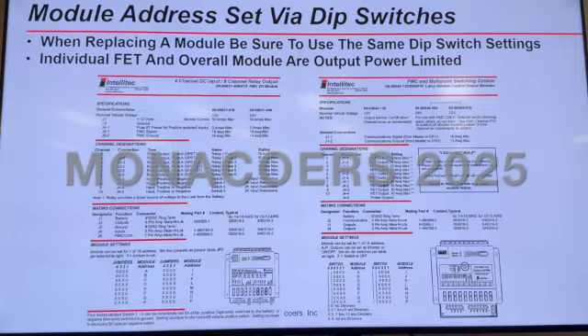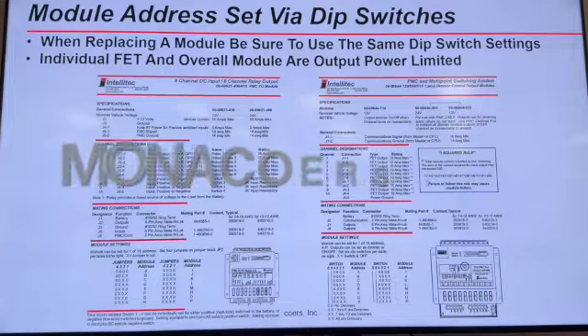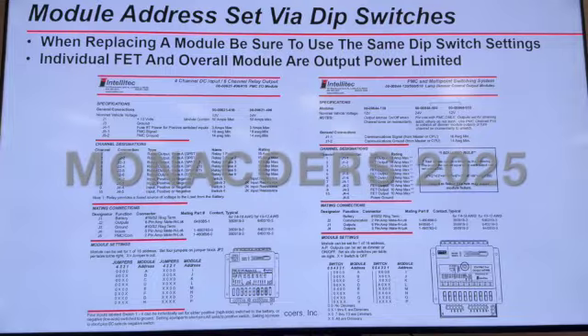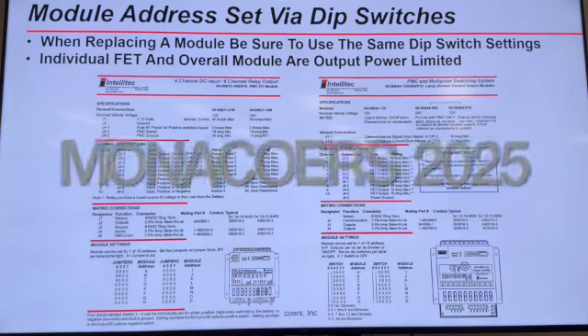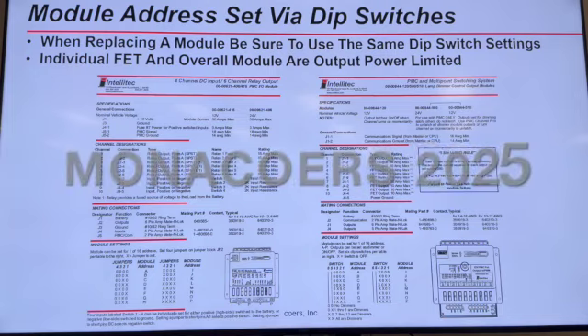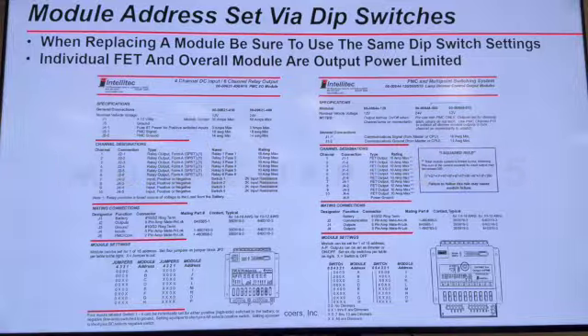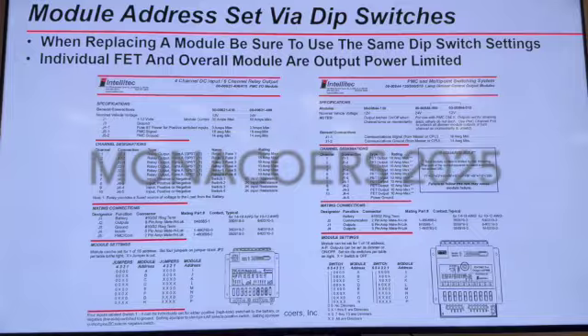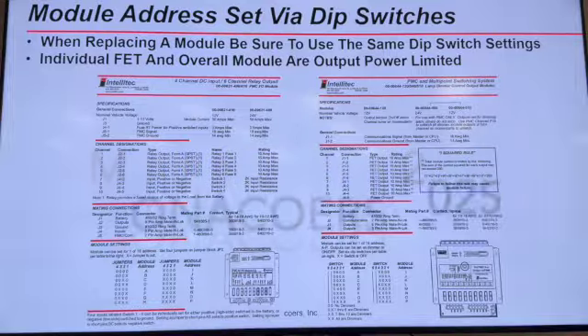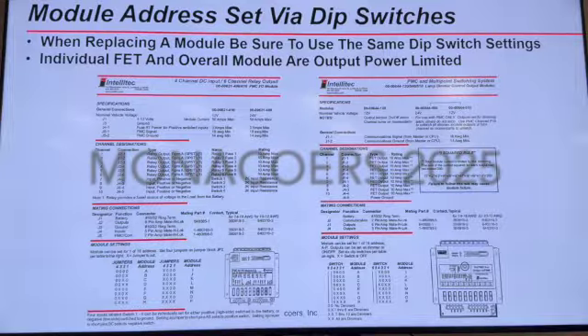Once you don't have enough power to run the module, you think it's the system, but it's not. You should go in and do your PM and tighten up all the terminals on the circuit breakers behind the whole thing. That solved it too. That's driven us crazy at least 4 times that I can remember.